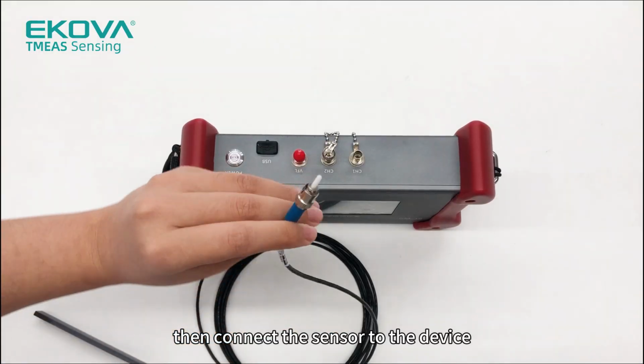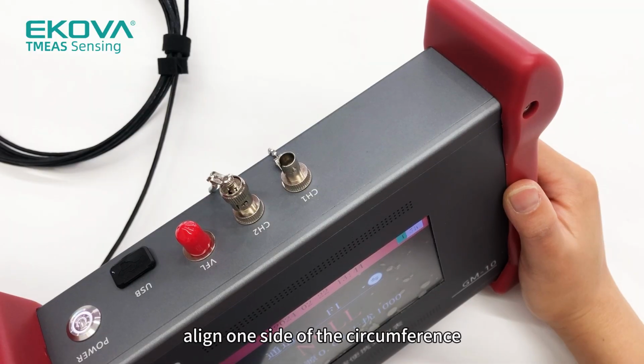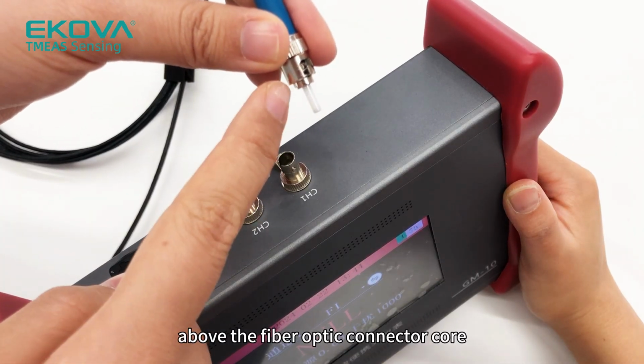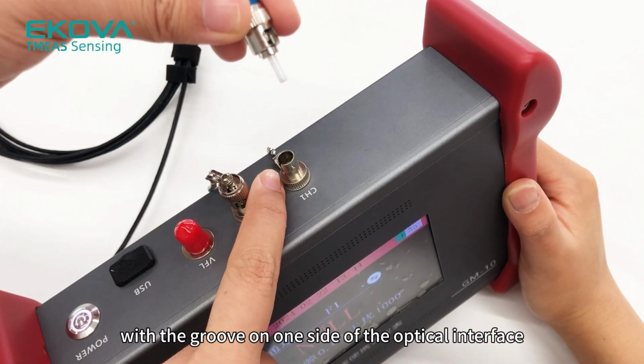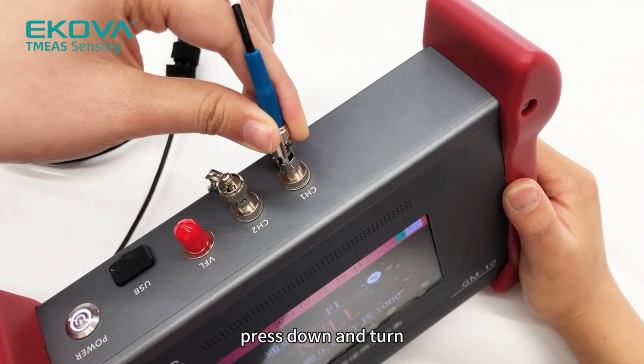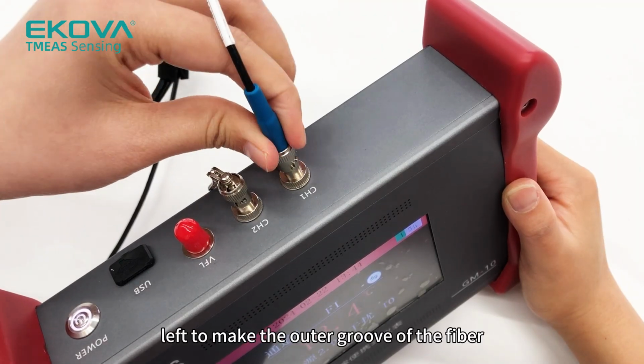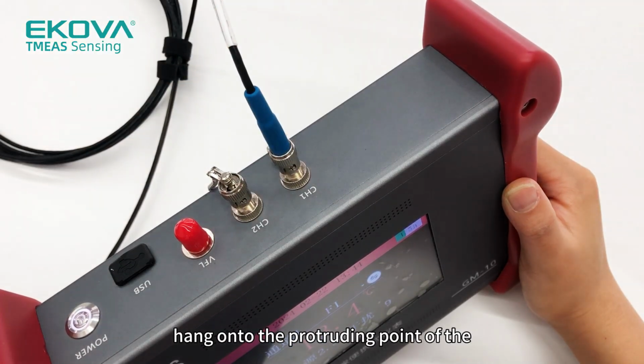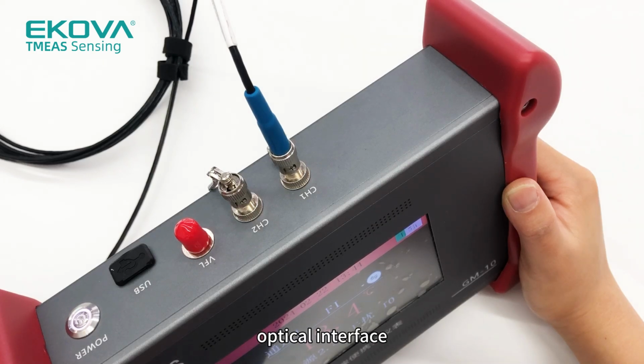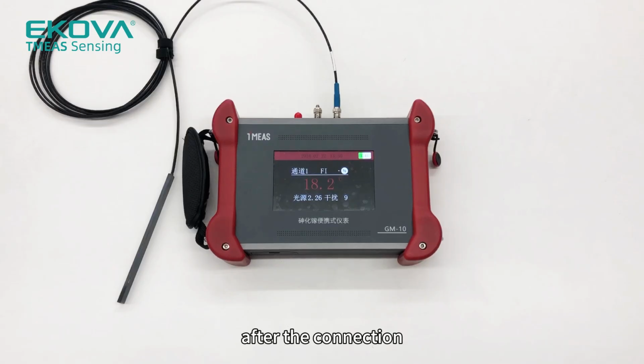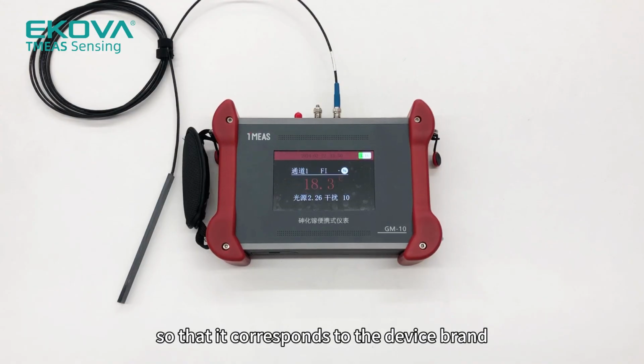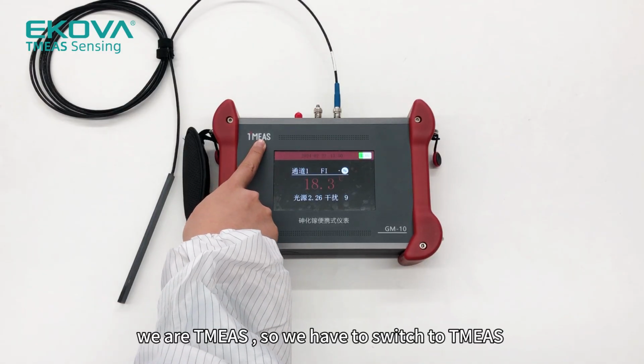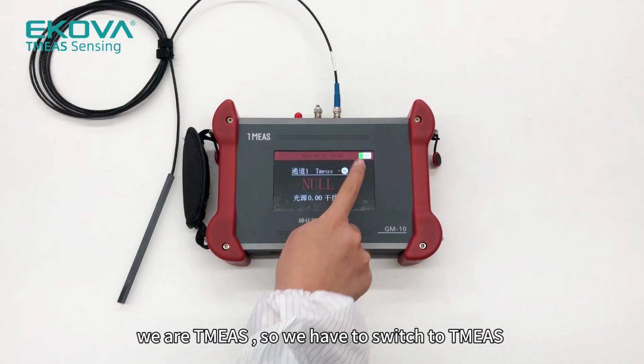Then connect the sensor to the device. Method: align one side of the circumference above the fiber optic connector core with the groove on one side of the optical interface. Press down and turn left to make the outer groove of the fiber optic connector hang onto the protruding point of the optical interface, and it is successful. After the connection, adjust the interface channel label so that it corresponds to the device brand. You can then detect the temperature measurement performance of the sensor. We are TMEAS, so we have to switch to TMEAS.